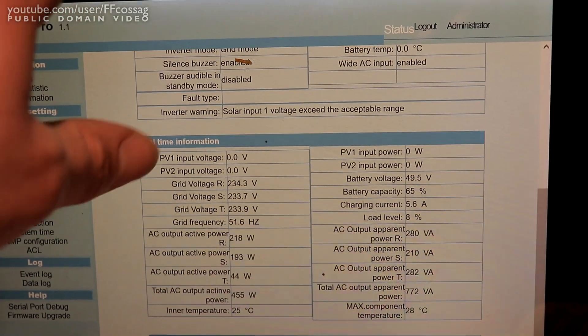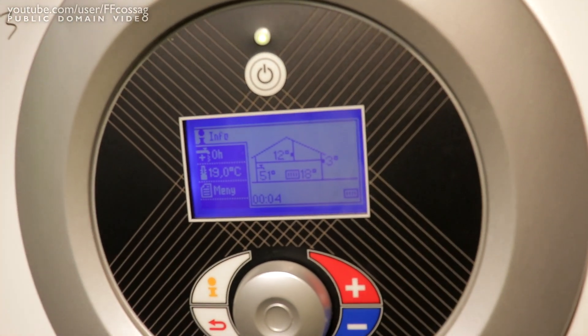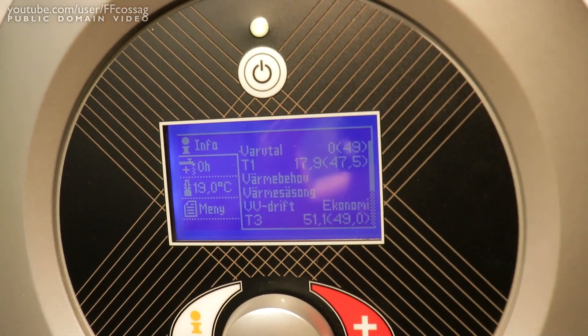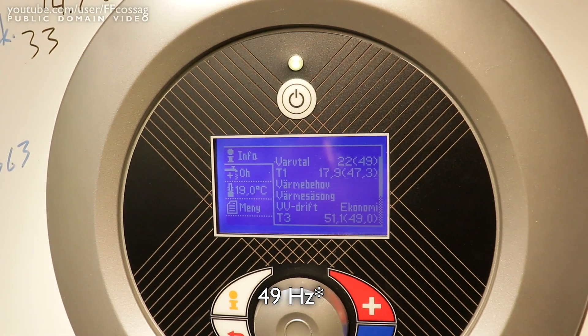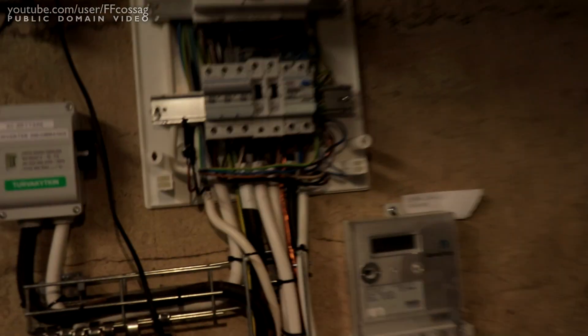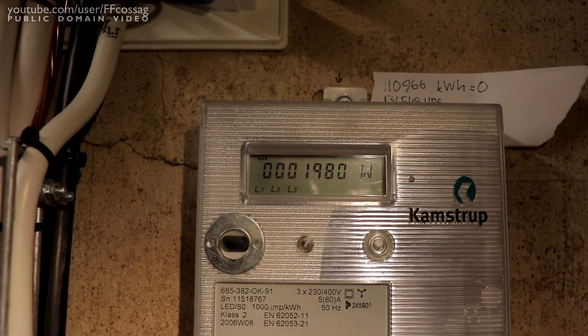We've got about 0.8 amps per phase. Let's see if we can start the heat pump. The heat pump is starting up — it's a big inverter unit, pretty harsh. The compressor's going, revving up, going up to 49 Hz. It seems okay, we're up to speed. Heat pump is using 1,800 watts... 1,900... about 2 kilowatts.